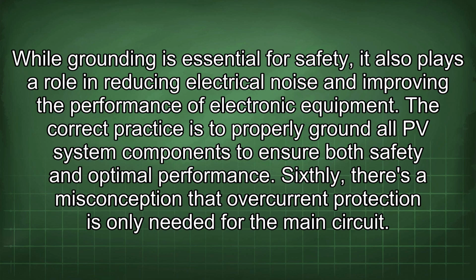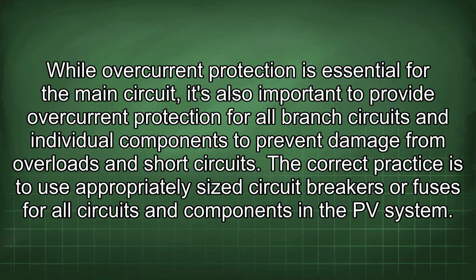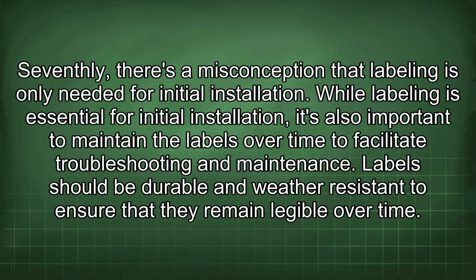Sixthly, there's a misconception that overcurrent protection is only needed for the main circuit. While overcurrent protection is essential for the main circuit, it's also important to provide overcurrent protection for all branch circuits and individual components to prevent damage from overloads and short circuits. The correct practice is to use appropriately sized circuit breakers or fuses for all circuits and components in the PV system. Seventhly, there's a misconception that labeling is only needed for initial installation.